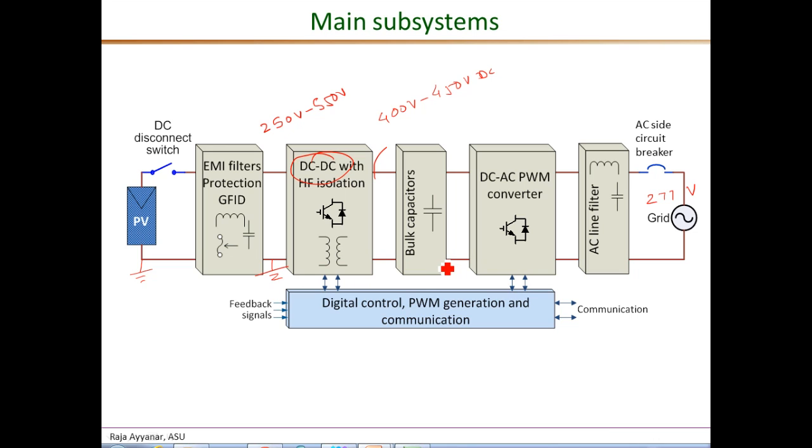We need these large bulk capacitors because in a single phase system the instantaneous power that is injected into the grid is pulsating. It is pulsating at twice the line frequency, 120 hertz in the US, whereas we want the power taken from the PV panels instantaneously to be a smooth continuous power so that we always operate at the maximum possible power from the PV arrays.